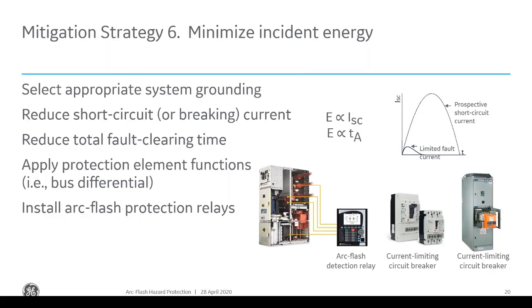And finally, to reduce the incident energy or arc flash energy, apply protection functions that are very fast and can trip the mechanism. So it's a combination of how fast the protection device senses the arc flash and how long the breaker takes to clear the arc flash or the fault condition that caused it. In addition to having faster breakers, we can install arc flash protection relays. They're not arc flash resistant relays, they're arc flash protection relays. The purpose is to reduce the total fault clearing time.